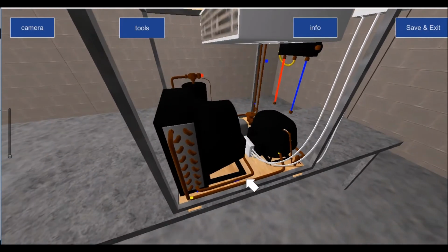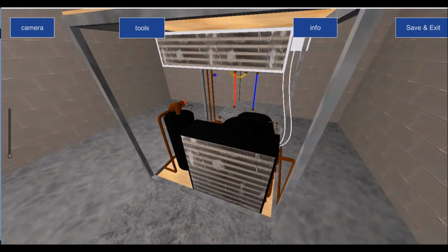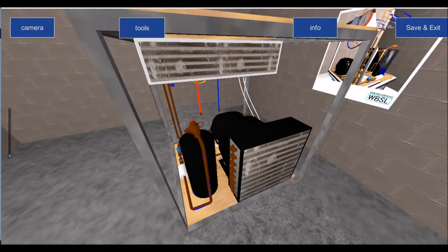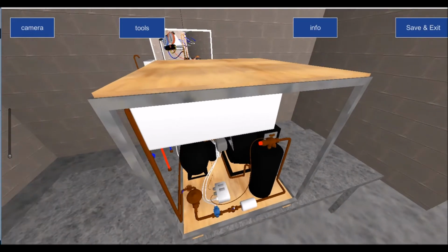Now, not all jobs have liquid receivers, but the liquid receiver is not a main component, it is a main accessory. So when I talk about components, there are only 4 main components that I'm concerned about with a vapor compression system, and everything else that you see is an accessory which has been fitted to engineer the system to make it more efficient or to make it serviceable. So we have the high pressure, high temperature subcooled liquid traveling along the liquid line, and it travels as far as the third component that we talk about. So we have compressor, condenser, metering device.